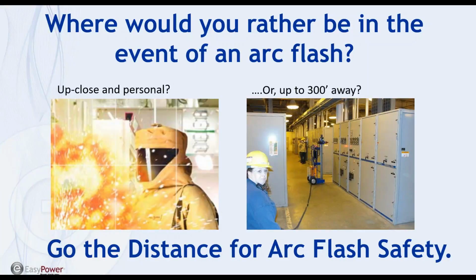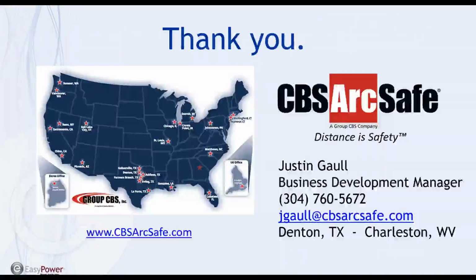Well, you're always measuring for voltage with the meter, that step is always going to require PPE and proper tools and voltage rated equipment to do that. Short of installing some permanently installed voltage detector or something, you're going to have that task. You just got to view these situations, there's always lots of things that can go wrong, and you got to do all you can to make the small steps safe.